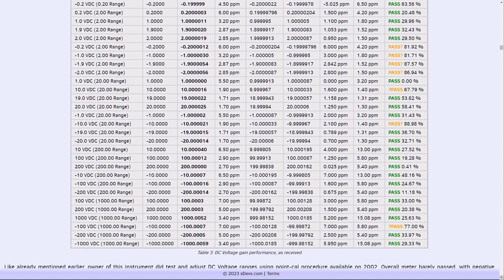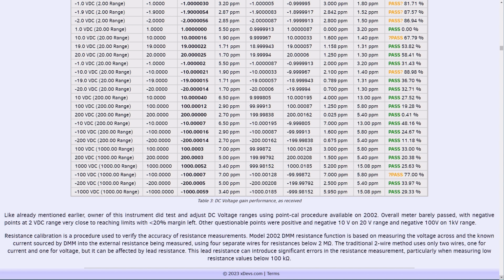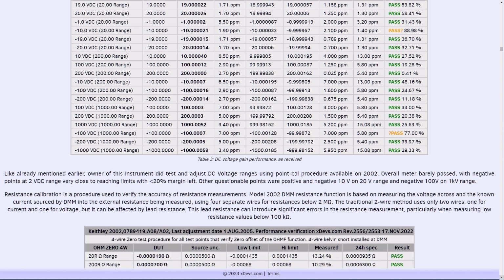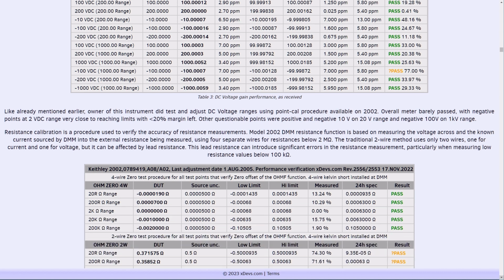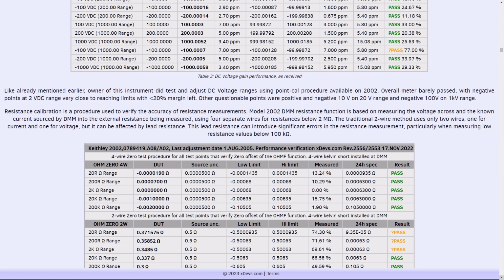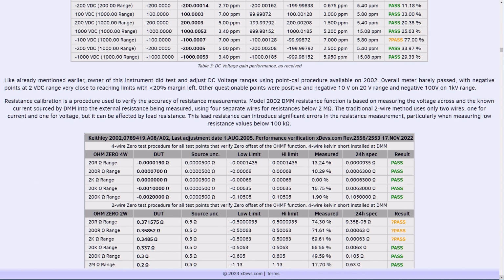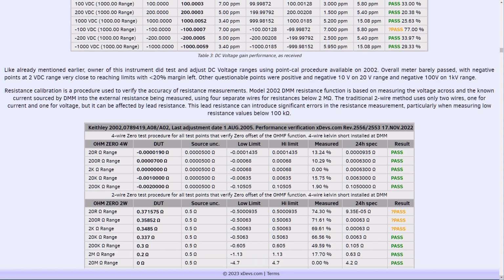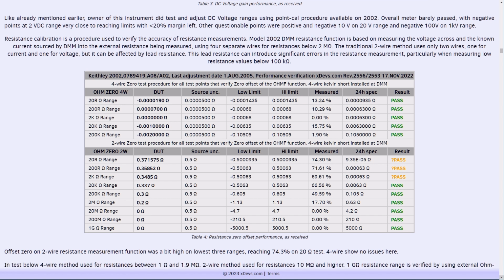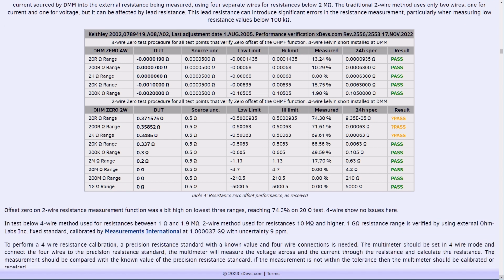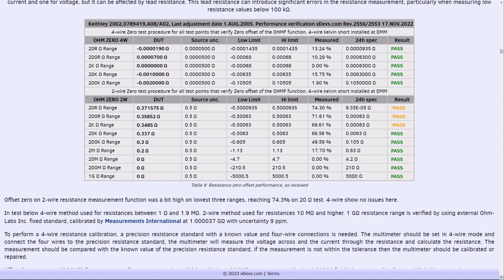Next test is 4-wire resistance measurement functionality. First we check zero offset on both 4-wire functionality and 2-wire for resistance ranges. Resistance zero offset verification gave us pretty good results, with a bit higher deviation on the 20 ohm, 200 ohm and 2 kilo ohm shorts in 2-wire mode. All these tests were done with a low thermal 4-wire short at the meter's input terminals.